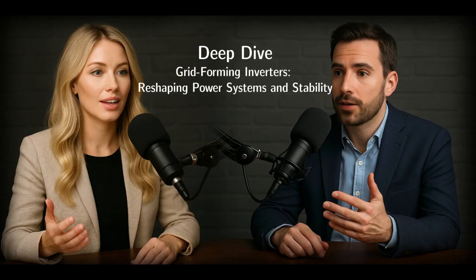They're doing quite a lot, providing that super fast primary frequency response, within about 150 milliseconds. They're injecting synthetic inertia, especially crucial during periods when wind and solar output is low and there isn't much traditional inertia online. They also provide dynamic reactive power support for voltage stability on the transmission system, and some are even being qualified for black start capability to help restore critical transmission corridors after an outage. So ERCOT is clearly recognizing the value. How are they integrating this into their market structures and paying for these services?